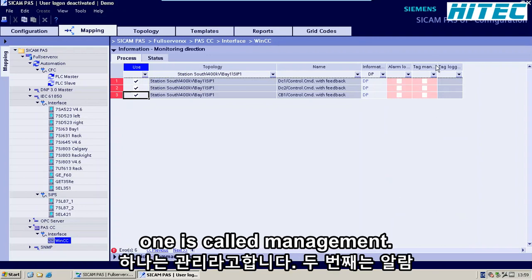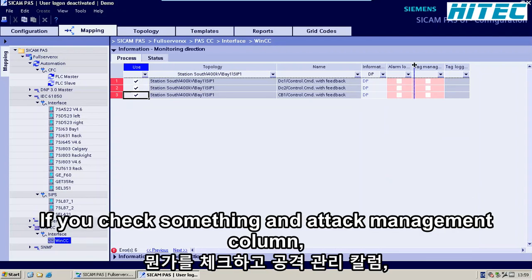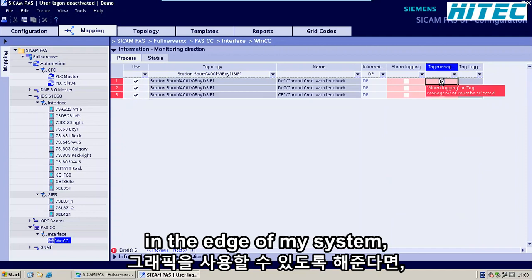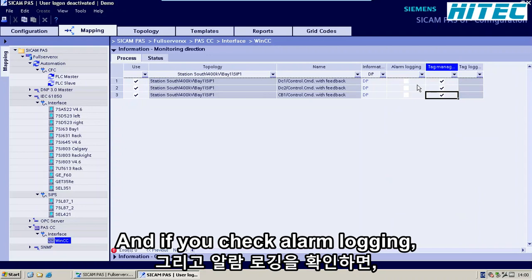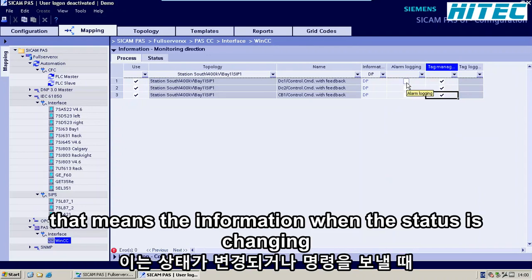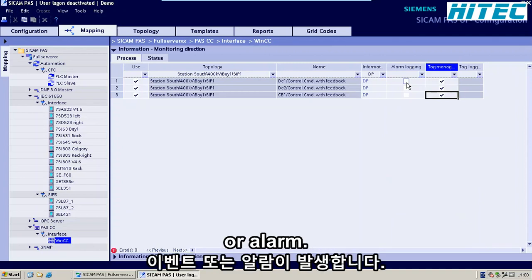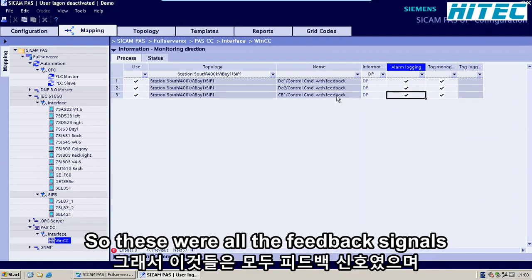If you check something in the Tag Management column, that means you make it available in graphics in the HMI system — so I want to use this information in the graphics. And if you check Alarm Logging, that means the information when the status is changing, or if you send a command, will go into the event or alarm list. So I want to see this in our event list as well. So these were the feedback signals.